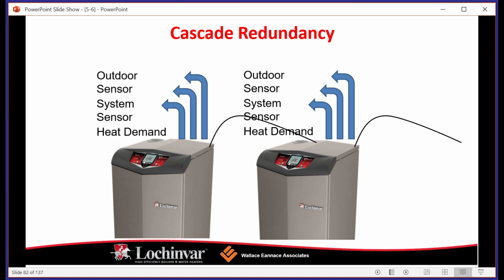So again, irrespective of whether you're using outdoor air or a system sensor for constant set point, this cascade redundancy is tremendously helpful. It helps our fuel efficiency, and it also gives you the peace of mind that if you do have a failure, or you need to shut down for service for one of the pieces of equipment, whatever the reason is, you never lose the building. And if any of you have ever been in a position where somebody value engineered their building too much, they had one boiler that went down in the wintertime, it's not pretty. So again, cascade redundancy is very, very important, and you almost never see a single boiler in anything outside of a residential application for that reason.